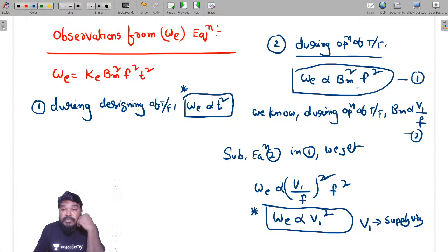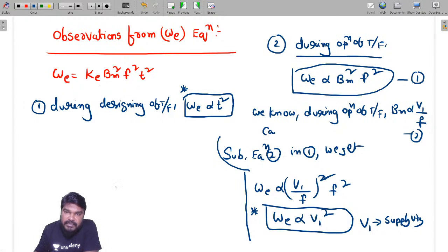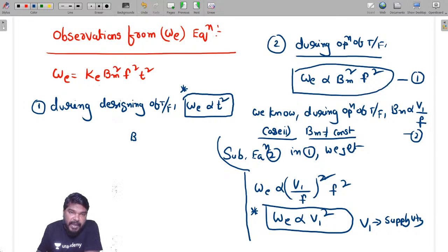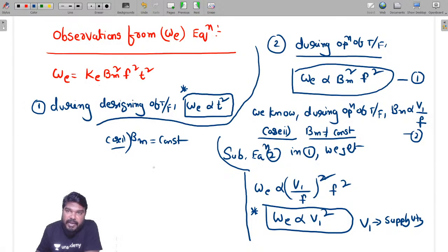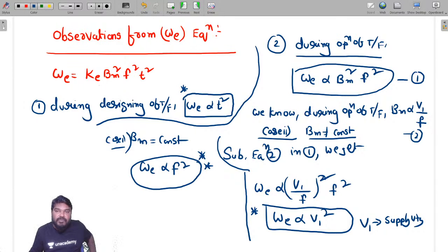During the operation, if B maximum is a variable, we can take this as case 2. Suppose B maximum is constant, like case 1. Then what will happen? When B maximum is constant, eddy current loss is directly proportional to the frequency square. So here we have two cases. In case 1, B maximum is constant, and eddy current loss is directly proportional to the frequency square. In case 2, B maximum is not constant, and eddy current loss is directly proportional to V1 square. All of you clear my point?